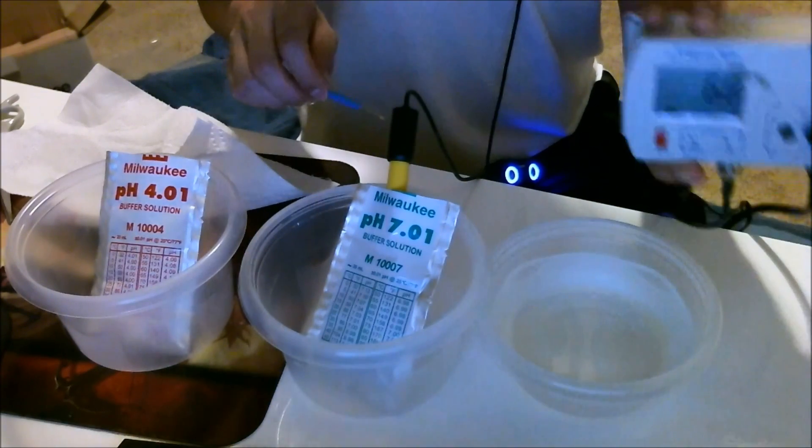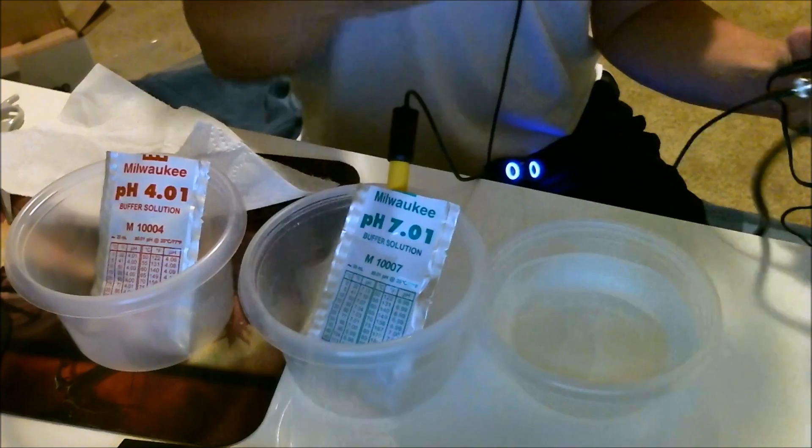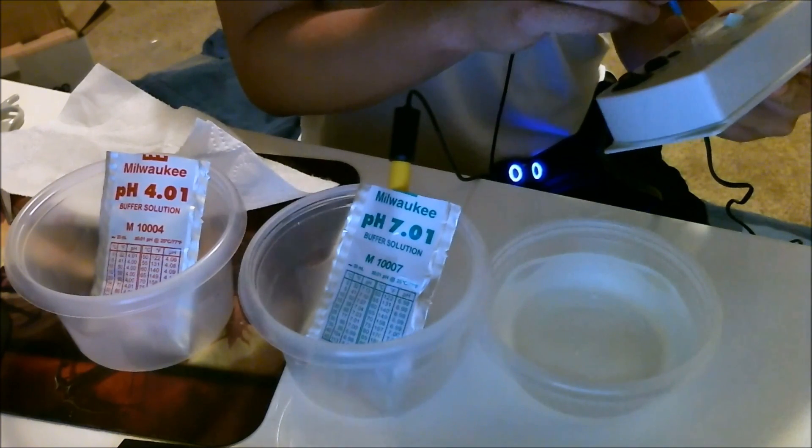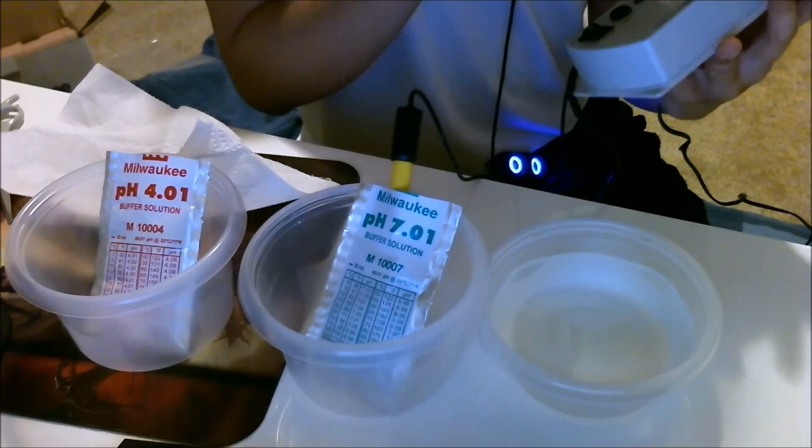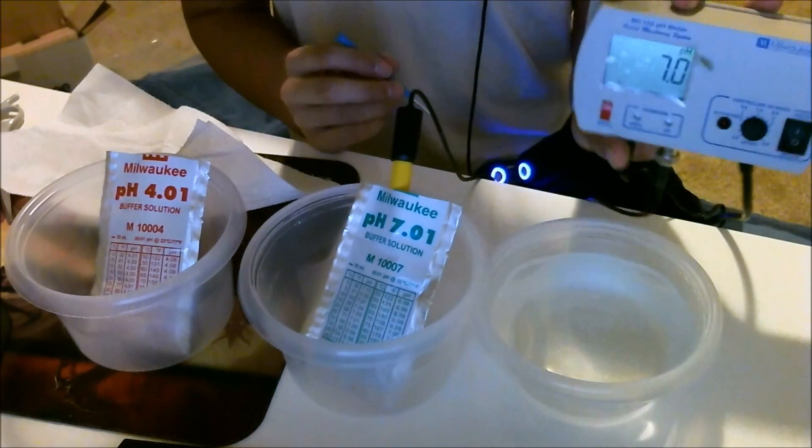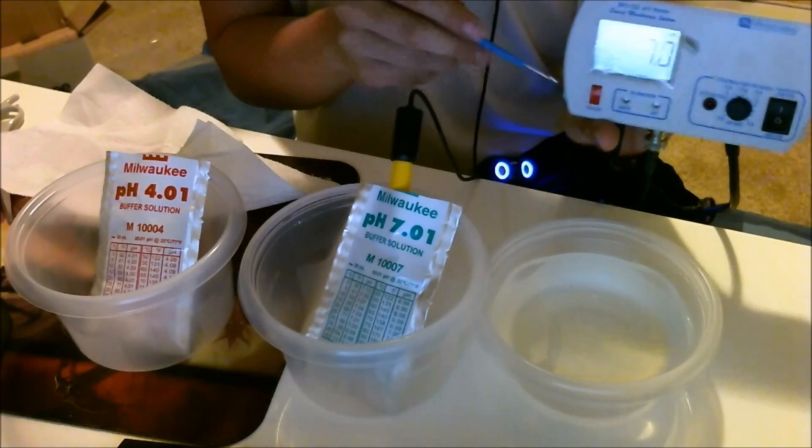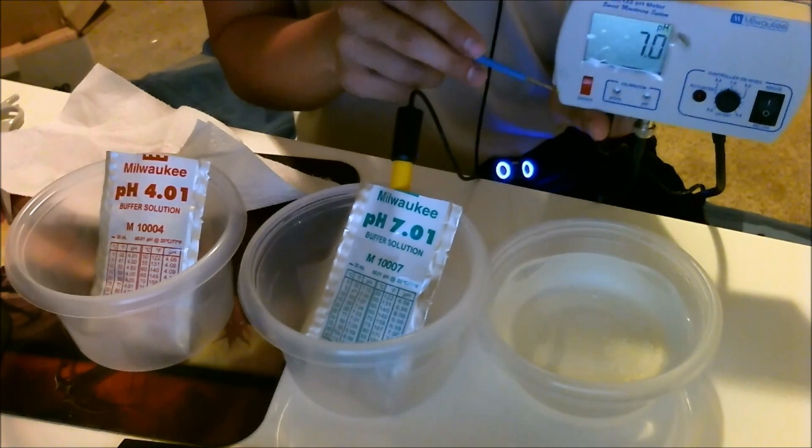Right now it's reading at 6.8, so it's actually really close. We're just going to play with the 7.0 until it hits. Now it's reading 7.0. All I did was adjust the 7.0 screw.